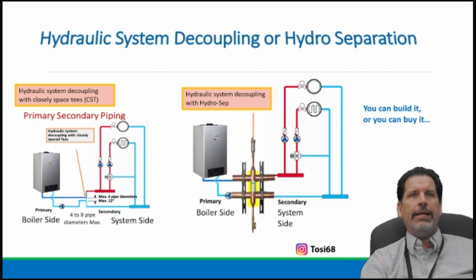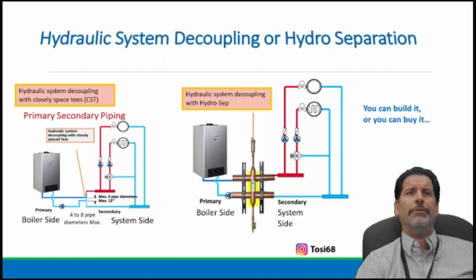So what do we need? We need appliances. Think about this, you build your boiler like it's the first one ever built every time you install one. You buy all the components, you know where they have to go, you have to connect them, keep the water in the pipe, and then vent it. There's that other side too. We're not even talking about venting, but that's a lost art, a talent in itself, making sure we get that right. That becomes a life safety part of what we're doing, we're in the comfort and life safety business when installing boilers.